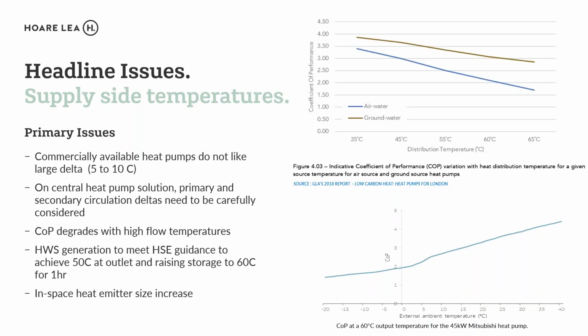Something that I think Dave will also cover a bit later, but also the issues you found with regards to heat pumps is obviously the temperature limitations and what happens when you start asking for high distribution temperatures with regards to COPs. And there you can see the difference between air and ground source with regards to the COPs in the top right hand graph.